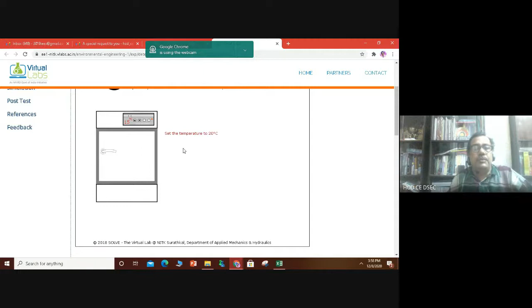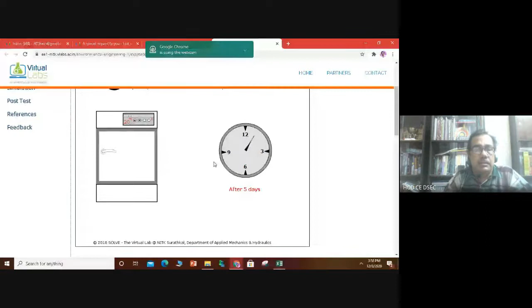you have to take the sample into the incubator. As I told you, this is a BOD incubator, where incubation takes place. If you go for the 5 day BOD, then you have to adjust the temperature to 20 degrees. If you go for the 3 day BOD, then you adjust the temperature to 27 degrees. Here we are going for the 5 day BOD, so we adjust it to 20 degrees and observe for 5 days.